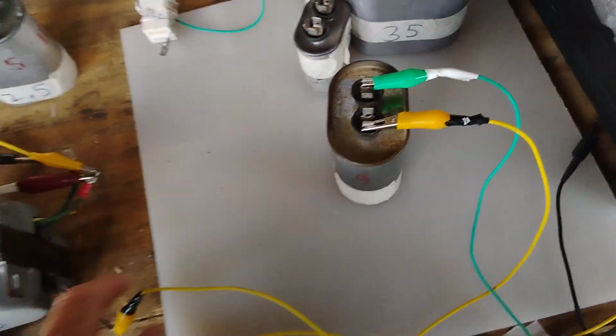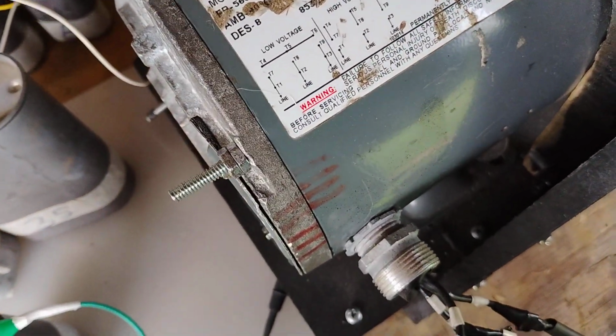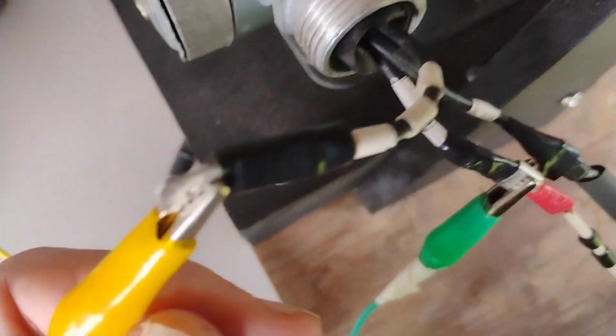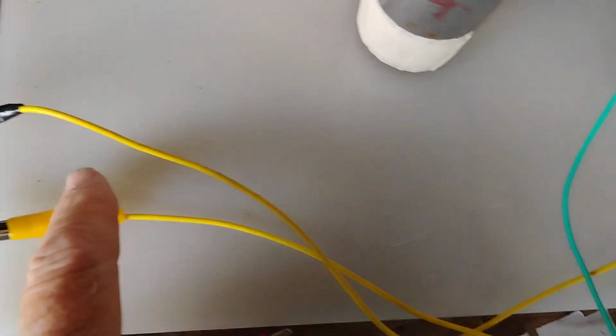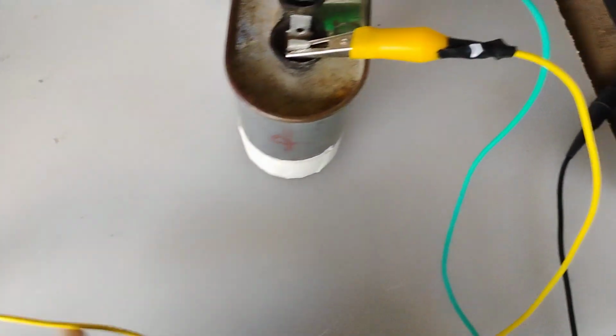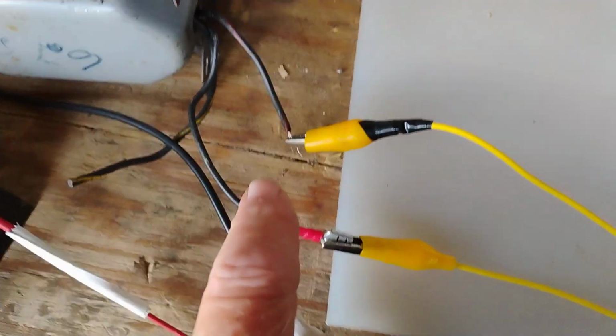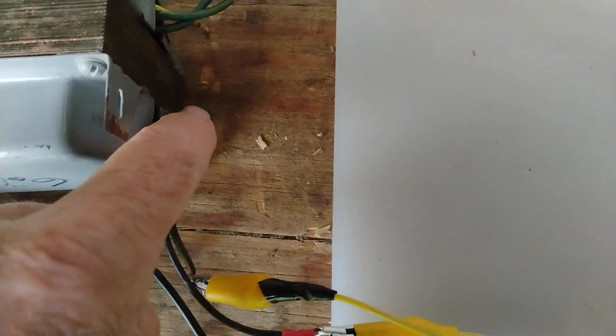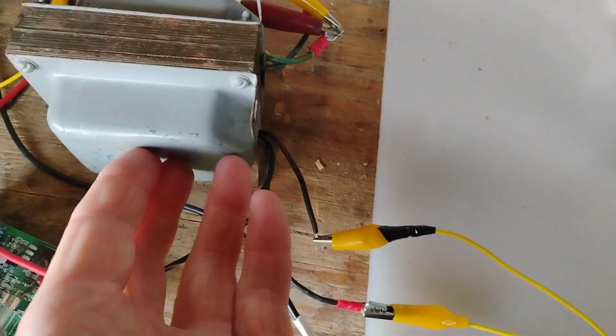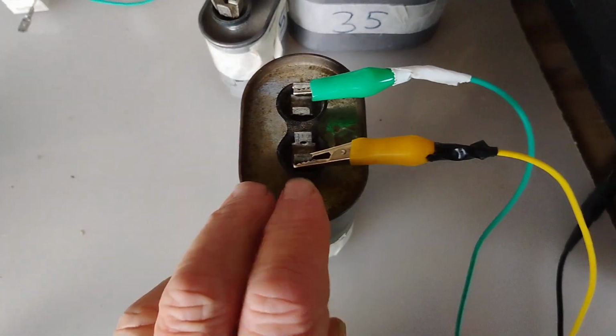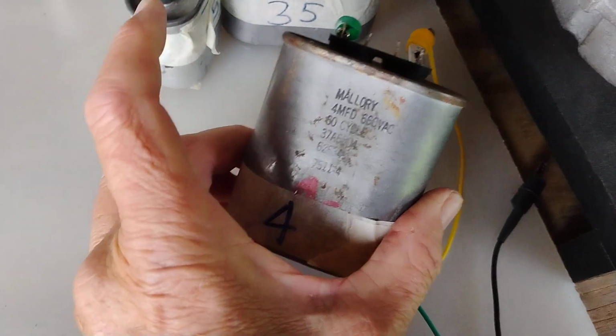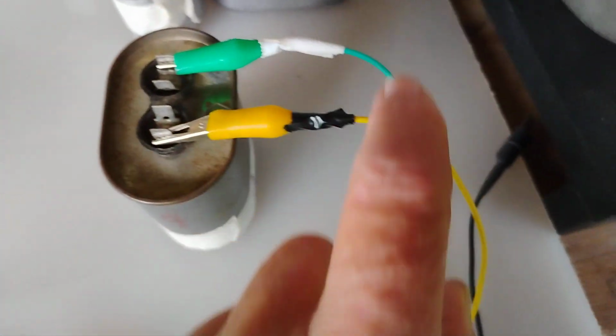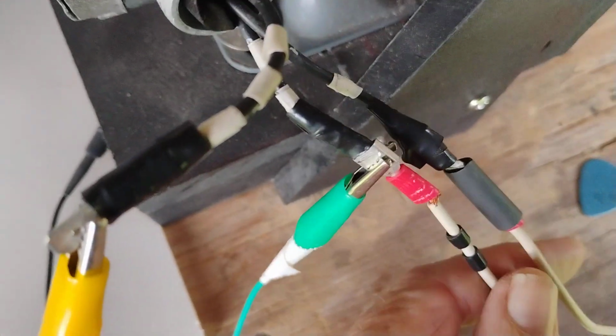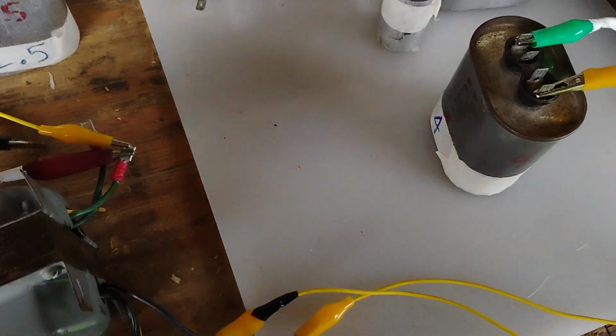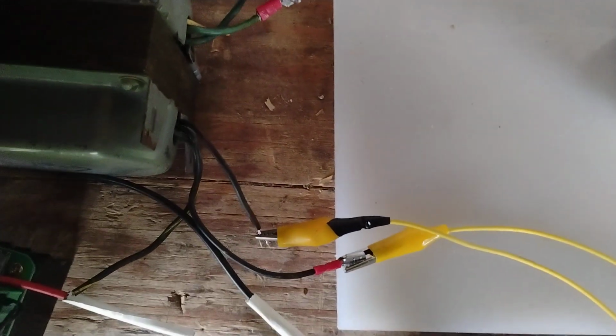Now what I've done is I've hooked this in series to the run cap. It comes off line 3, goes in one side, comes out the other, goes in one side of the transformer, comes out the other side of the same primary, and goes to one side of the run cap, 4 UF. That goes to line 2, which shares with the input. So it's a transformer in series. I guess you'd call this vectoring.